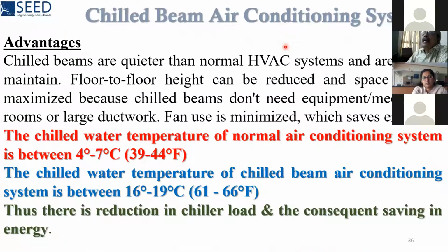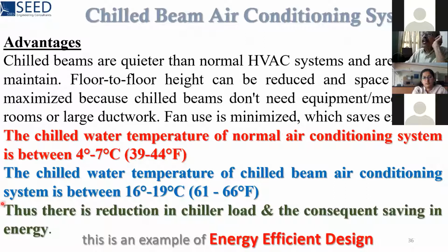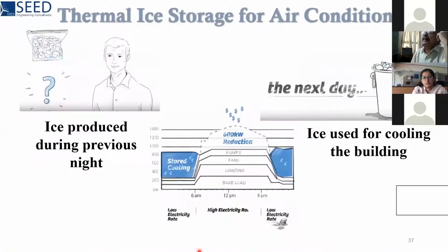How? Because in a normal air conditioning system, chilled water has to be cooled by the chiller in the range 4 degrees to 7 degrees centigrade. But chilled water in a chilled beam need be cooled only to 16 to 19 degrees centigrade. So you need not cool it down to 4 to 7 degrees. Thus there is a reduction in chiller load and a consequent saving in energy. So this is an example of energy efficient design.